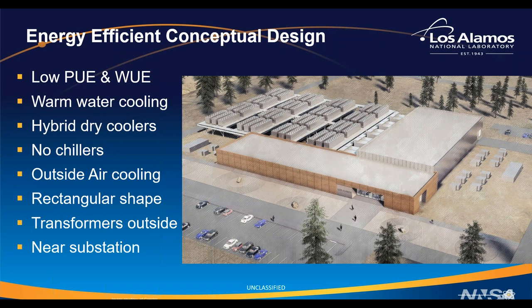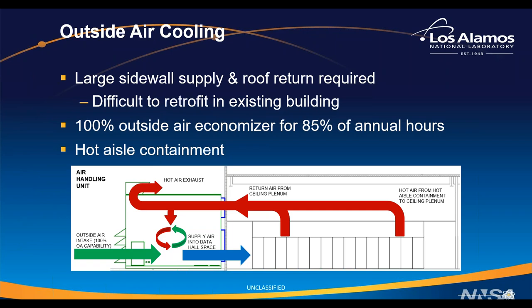Let's look in a little more detail at the concept of outside air cooling. Starting in the lower left-hand corner of that figure, the green arrow represents outside air coming into the data center. It's pumped and flooded into the data center, and then we have hot aisle containment represented by the red arrows that take the heat out to the hot air exhaust, as you follow that red arrow to the left, and that's exhausted outside.